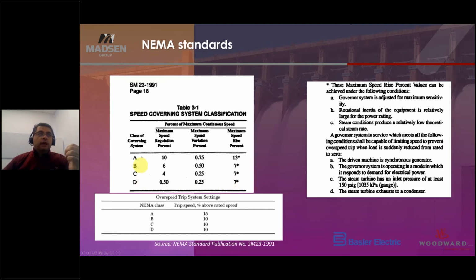So when we design a mechanical or electronic governor, we work with these standards, which are NEMA A or NEMA D. And you might see them in the newest electrical governors; you can see we are always working with NEMA D. You can see them in some of the mechanical governors too. It depends how old the governor is, whether it predates the standards or not, but that's the reality of the standard. And to be honest, these standards were also driven by other applications like steam turbine and gas turbine applications, so they came from many requirements, not only from the hydro turbine world.